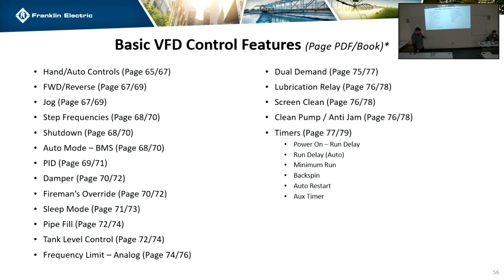Provides runtime, or just max it out, I guess. Okay. So it's going to ask you if you want a delay time. Basically, that's just a confirmation. If it doesn't see the end switch in this amount of time, it's going to assume there's a problem and trip. It's going to ask you what output terminal you want to use. So you can route your power through the drive, through an output relay to your damper, which will physically control the power. And then it's going to ask you what input you want to look for your end switch.